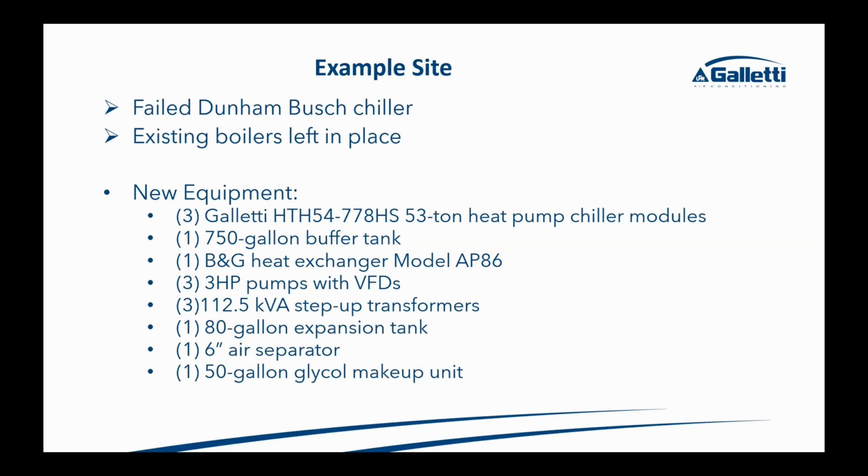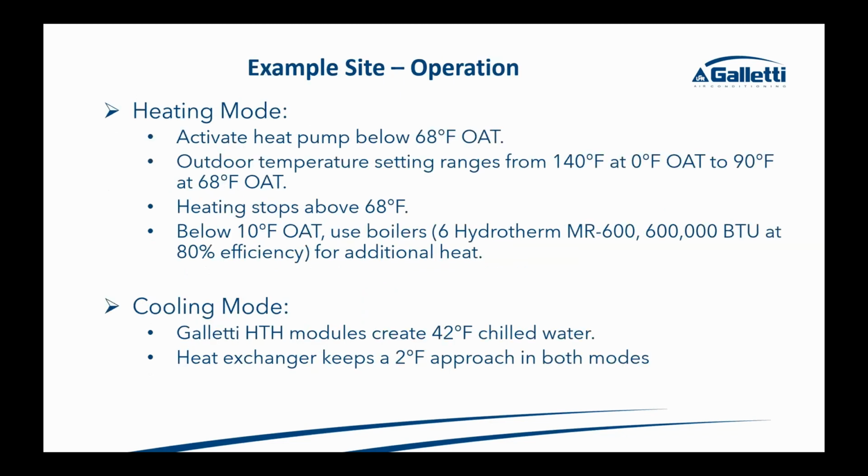They needed a lot of new things. So they needed new pumps, expansion tanks, air separators, a lot of stuff that was dated in the system. And so we put the quote together of all of these different components. And actually, I'll show the price breakdown in a moment. So those are all the items that we replaced. They left the existing boilers for now.